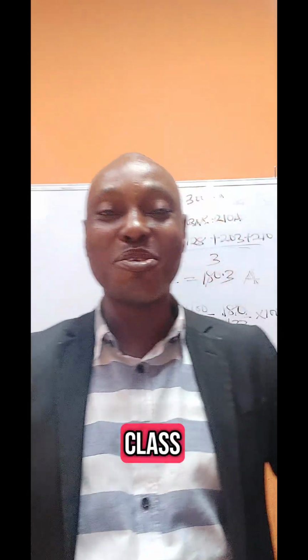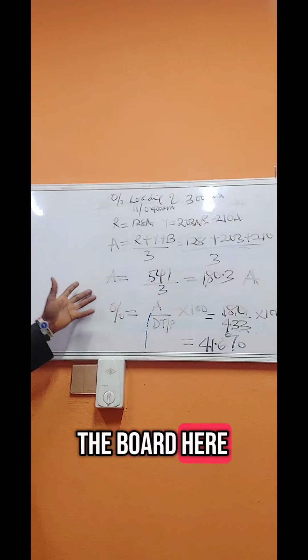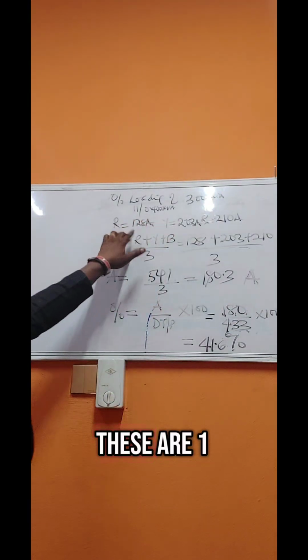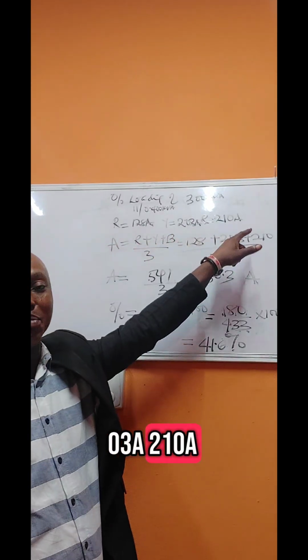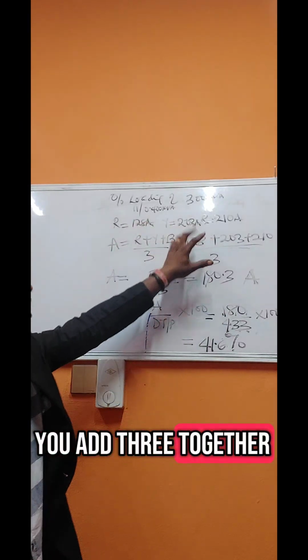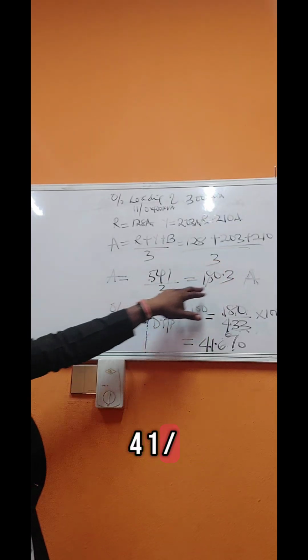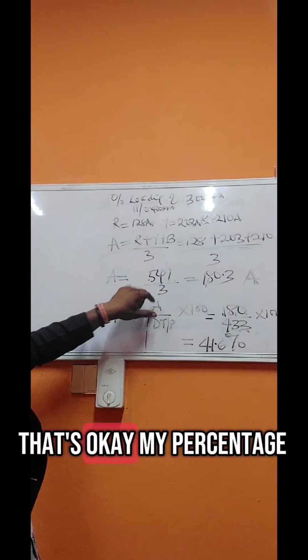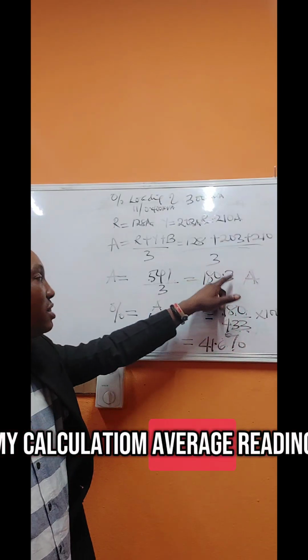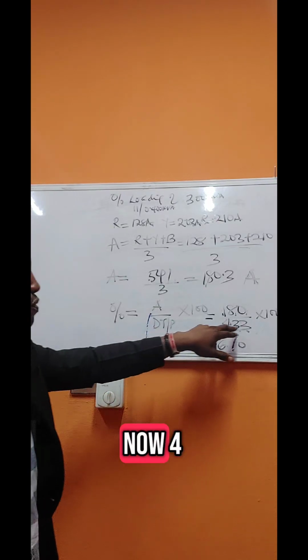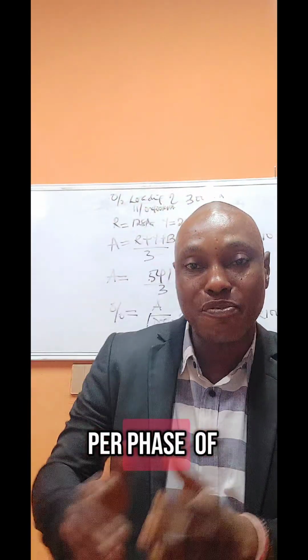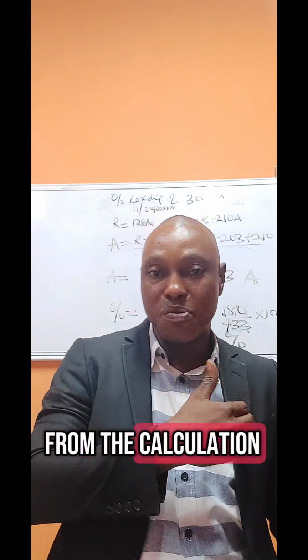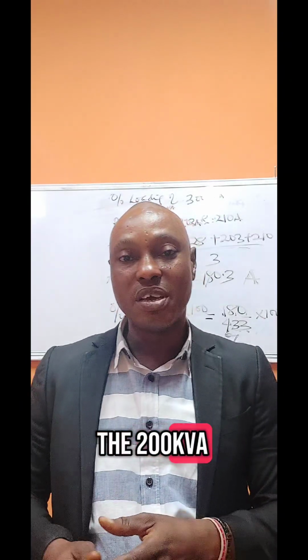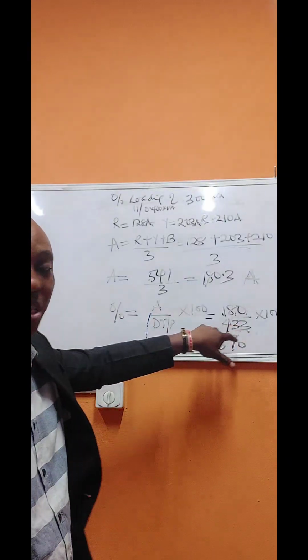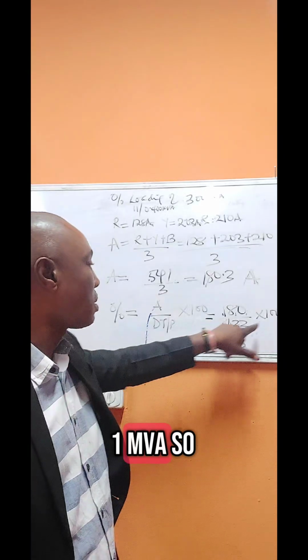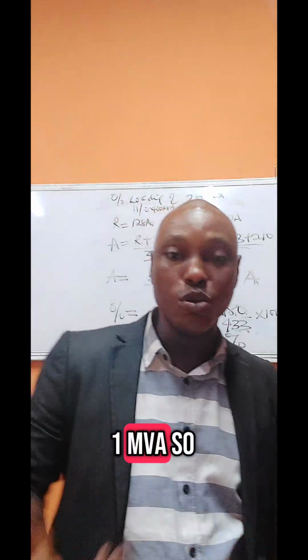Are you following? Welcome back to our class. The calculation for 300 kVA is what you are seeing on the board here. You can see the percentage for 300 kVA here. The readings are 128 amps, 203 amps, 210 amps. You add the three together and divide by 3. It gives you 541, divided by 3, 180 amps. Then for my percentage calculation, the average reading is divided by 433, which is the load per phase of a 300 kVA transformer. I told us you can get it for 200 kVA, even for one MVA. Then multiply by 100. So this transformer is giving 41.6% loading. So it's not overloaded as well.